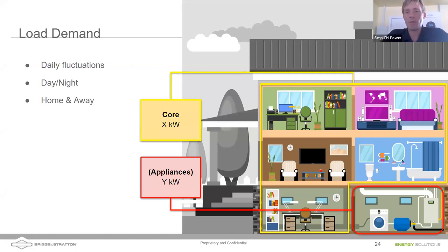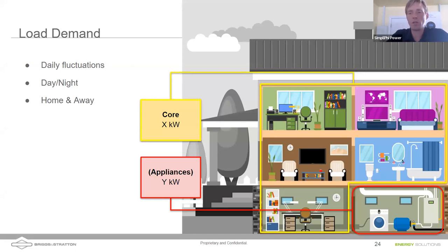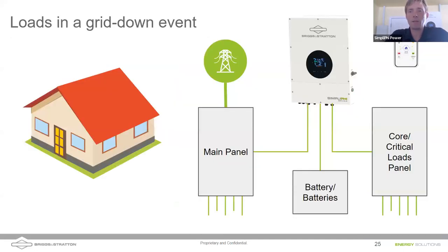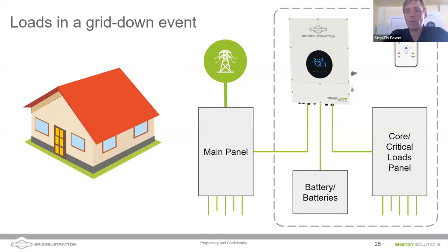During an outage, you probably won't want to back up everything. The main panel becomes isolated from the inverter to prevent sending power back to the grid where workers could be on the lines. Batteries then discharge through the inverter to power critical loads. Our inverters require a critical loads panel to be installed, though other options like the Sol-Ark 15K do not.